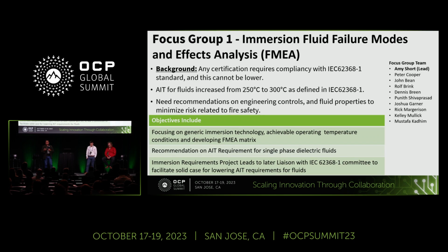That was published for 250C. But now, because IEC is already built in for all the dielectric fluids that come into play for certification, that was published as a 300 minimum AIT value. So to harmonize this, we raised the AIT values to 300.